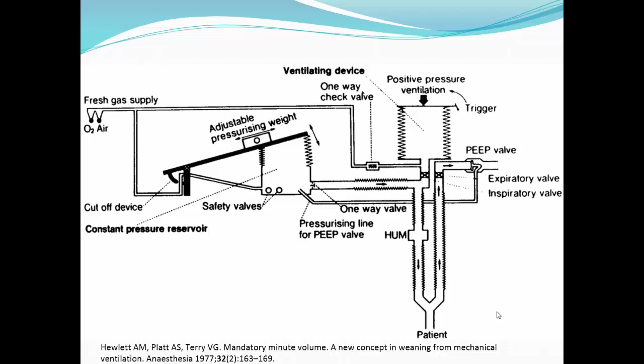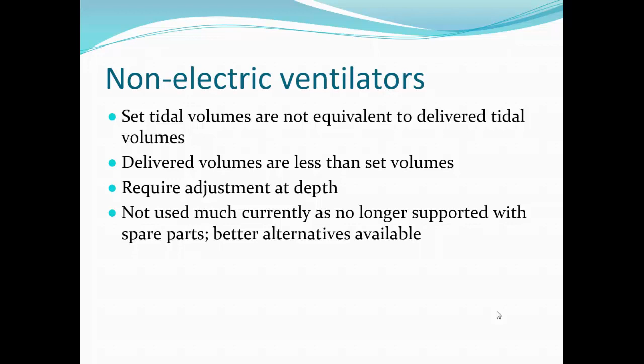So some of the issues with these ventilators, though: the tidal volumes that you set are not equivalent to the tidal volumes that are delivered to the patient when you're 45 feet under seawater. The volumes are much less. It requires constant adjustment at depth, and unfortunately, these non-electric ventilators are just not used as much anymore because you have better alternatives, and finding replacements and spare parts for them is becoming very difficult. So they're becoming more of just a museum piece now.